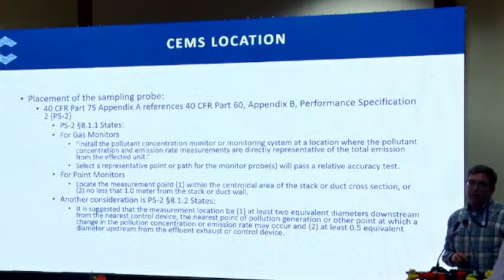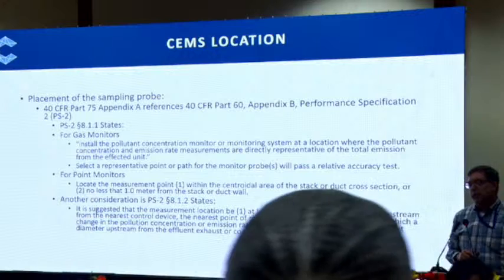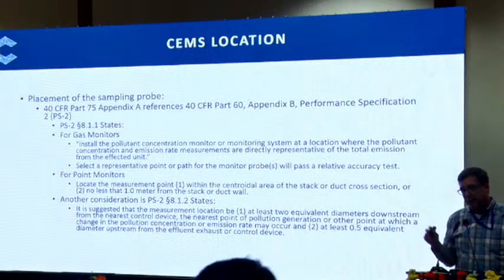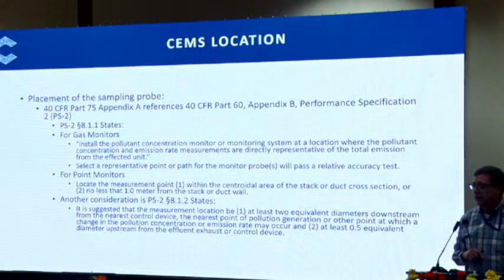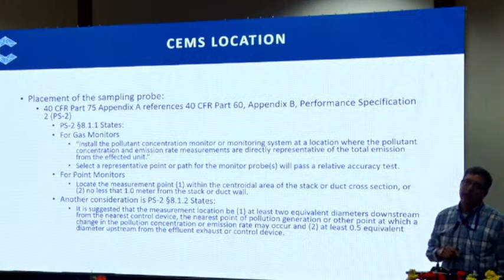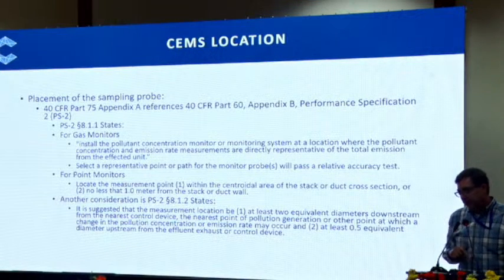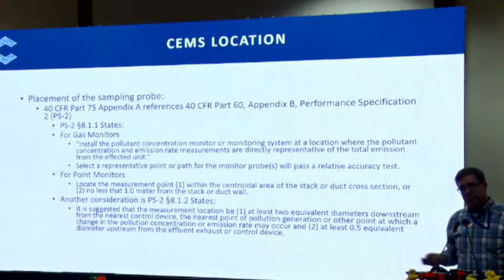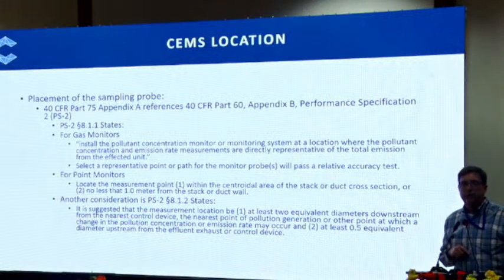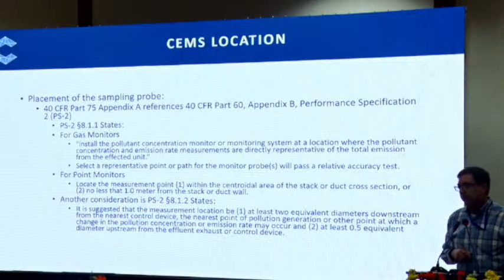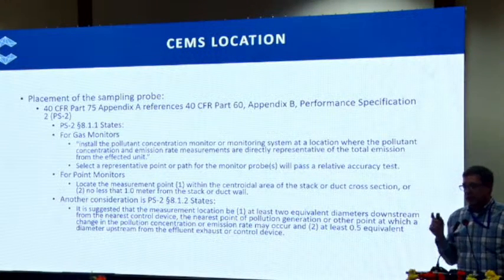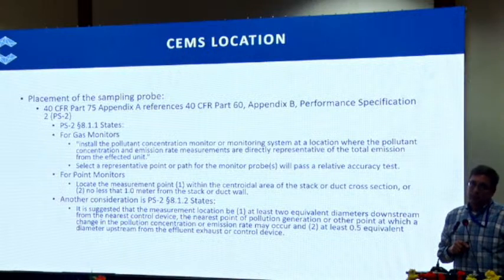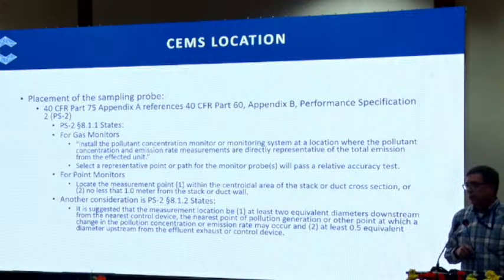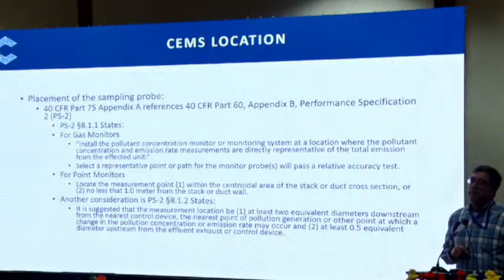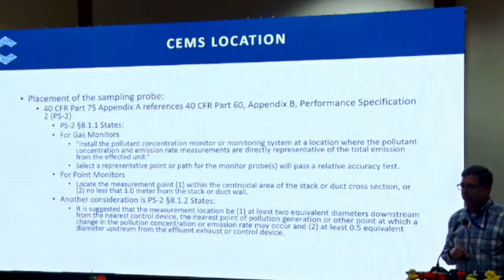So the placement of the sampling probe is a little bit different. We're not quite as prescriptive. I mean, there are some ideal measurements. You would ideally place it at 8 diameters downstream and 2 diameters upstream. However, the placement of the sampling probe, according to the EPA, allows for you to place the probe at a representative point.